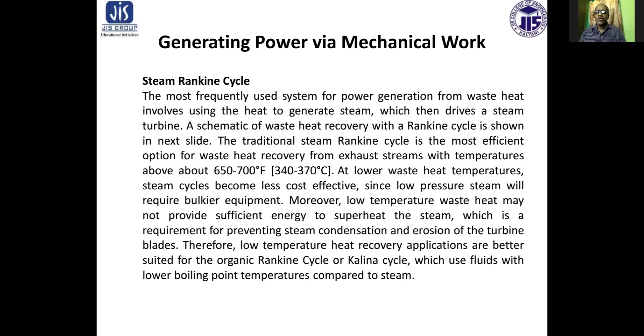At lower waste heat temperature, steam cycles become less cost effective since low pressure steam requires bulkier equipment. Moreover, low temperature waste heat may not provide sufficient energy to superheat the steam, which is required to prevent steam condensation and erosion of the turbine blades. Therefore, low temperature heat recovery applications are better suited for the organic Rankine cycle or Kalina cycle, which use fluids with a lower boiling point temperature compared to steam.